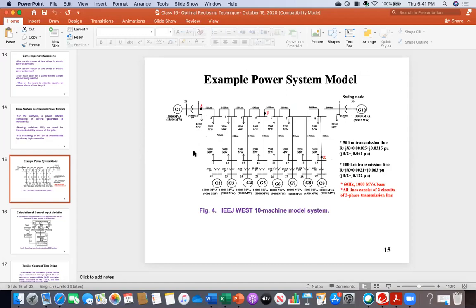It may happen that a point is critical but not all generators go out of step, only a few. Or it might happen that none of the generators become unstable, they just oscillate. So the critical point may differ depending on the system, but for this specific system, if a fault happens at point A, all 10 generators go out of step - that's why you must put a braking resistor here.